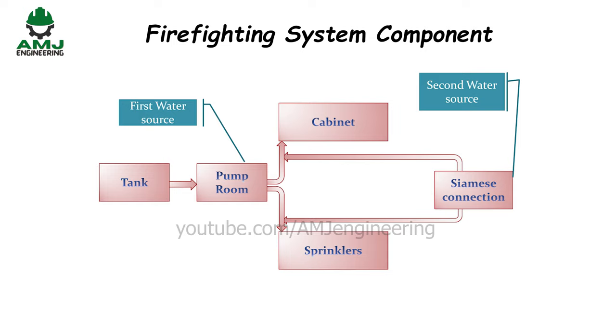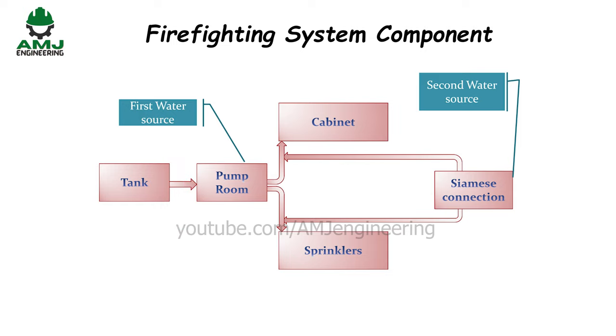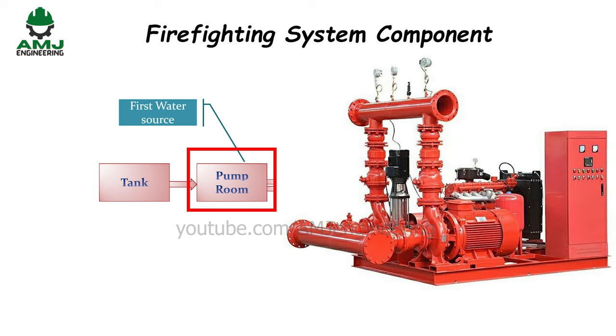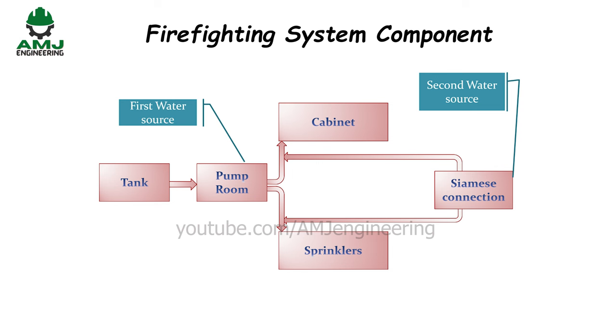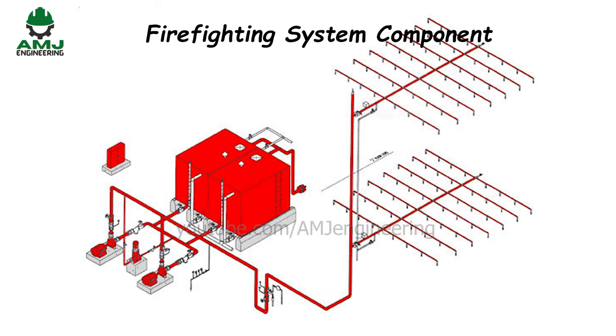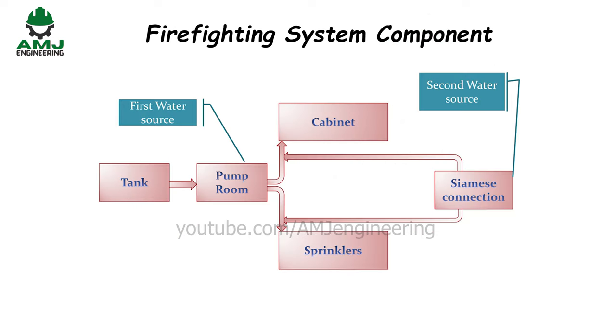In any building, the system consists of three basic parts: a large store of water in tanks, either underground or on top of the building, called fire storage tanks; a specialized pumping system, which usually includes three types of pumps — jockey pump, electric pump, and diesel pump; and a large network of pipes ending in either hydrants or sprinklers. Nearly all buildings require both of these systems.